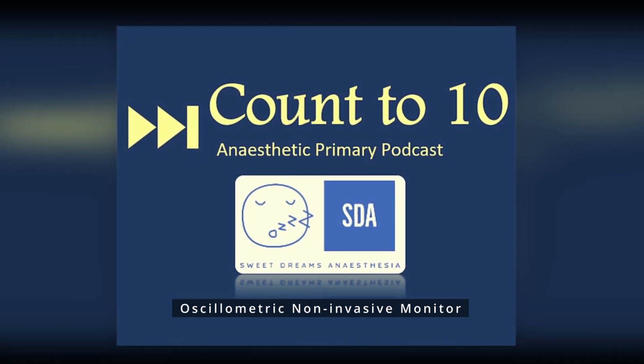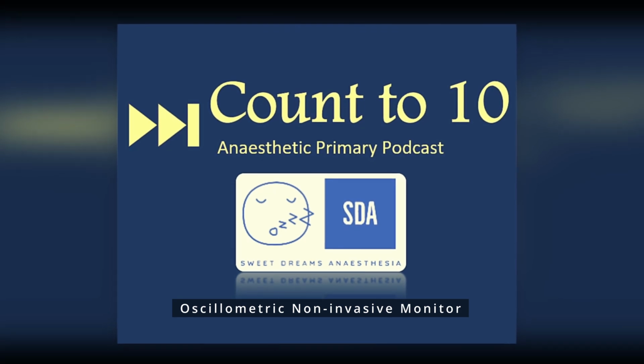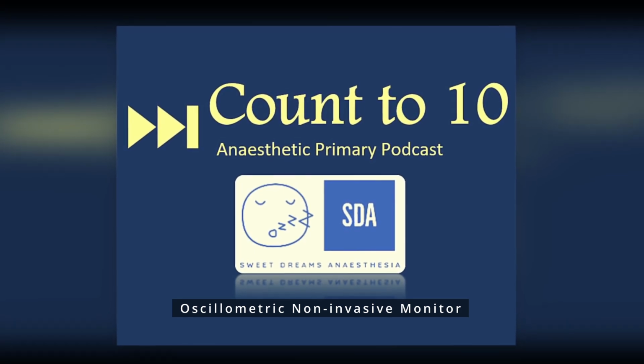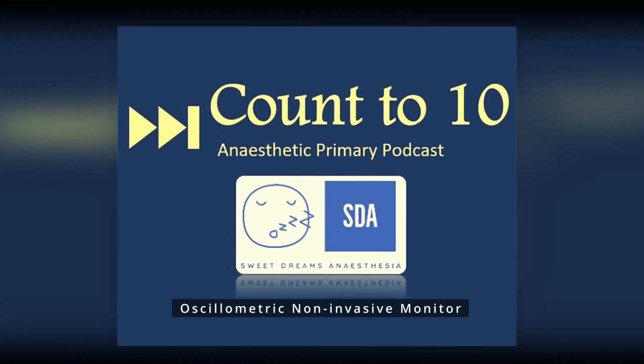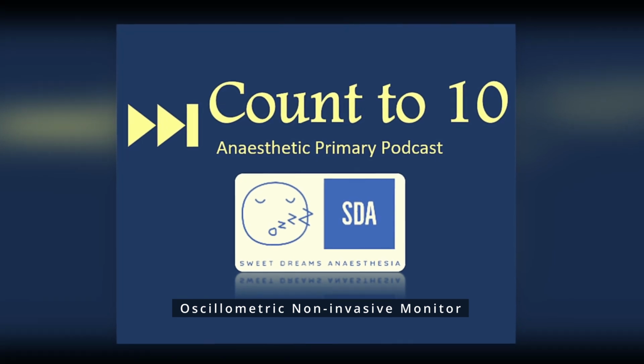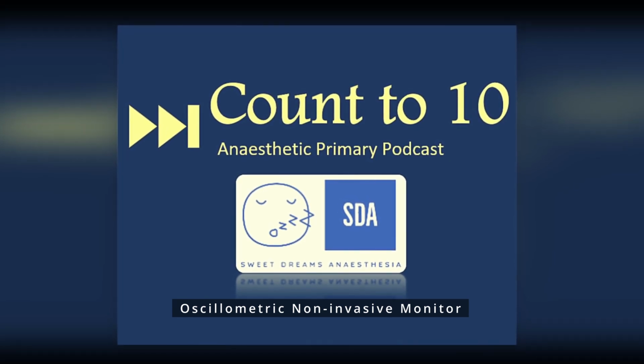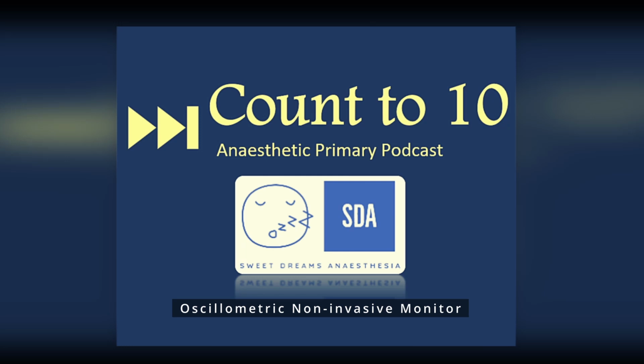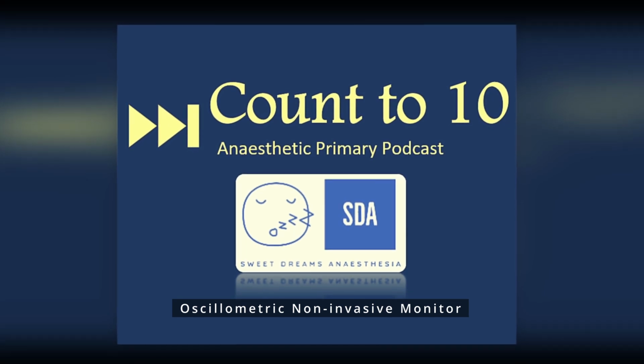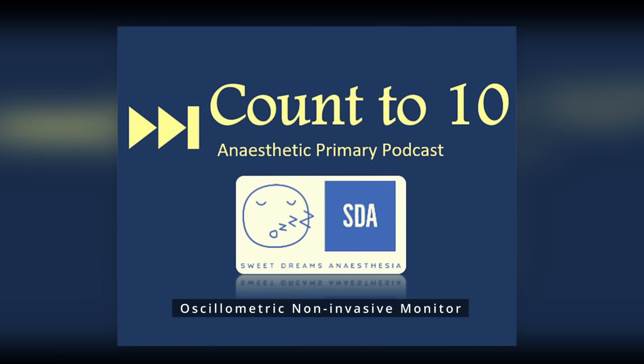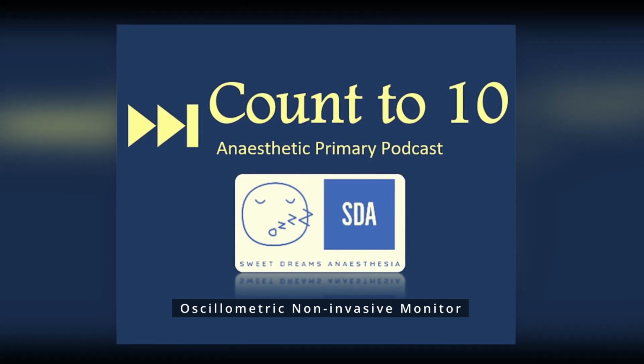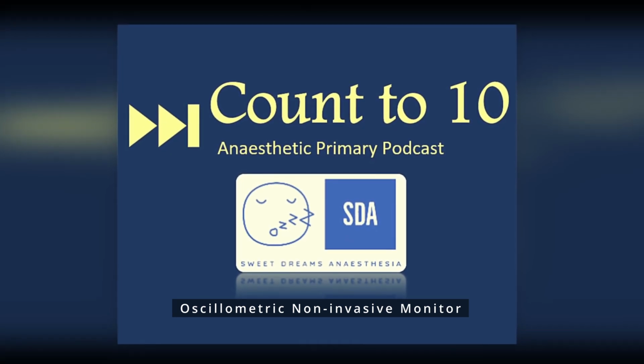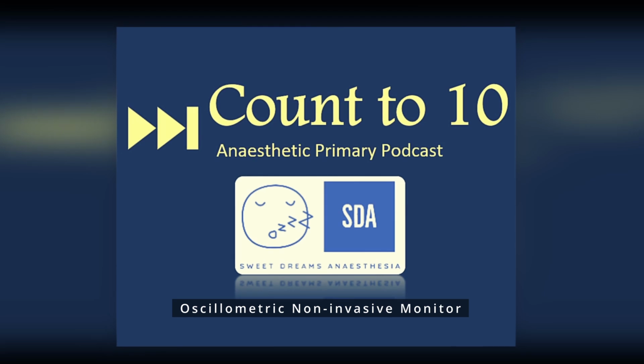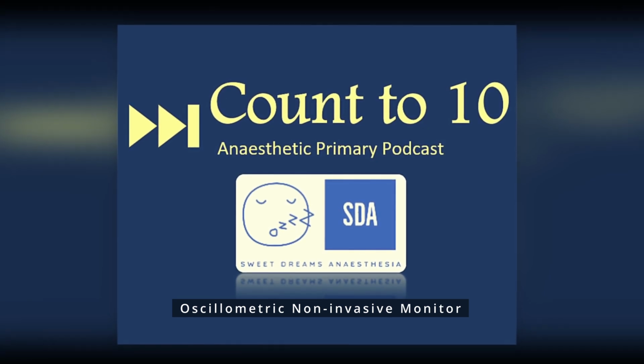The third technique is to note the point when the amplitudes of oscillations are in their fixed portion. This means that the amplitudes aren't increasing or decreasing. Now, because of the way we measure each one of these components, we typically say the most accurate measurement is the mean arterial blood pressure. This is followed by the systolic blood pressure, and then lastly by the diastolic blood pressure.